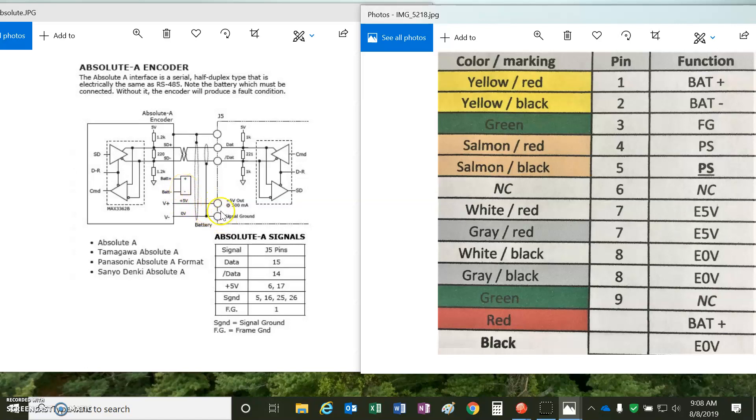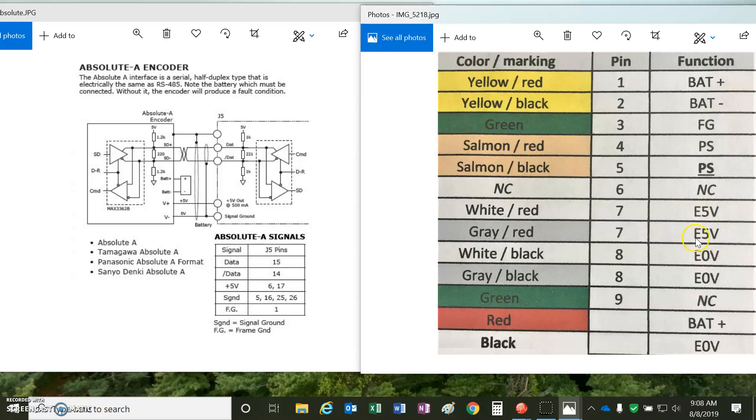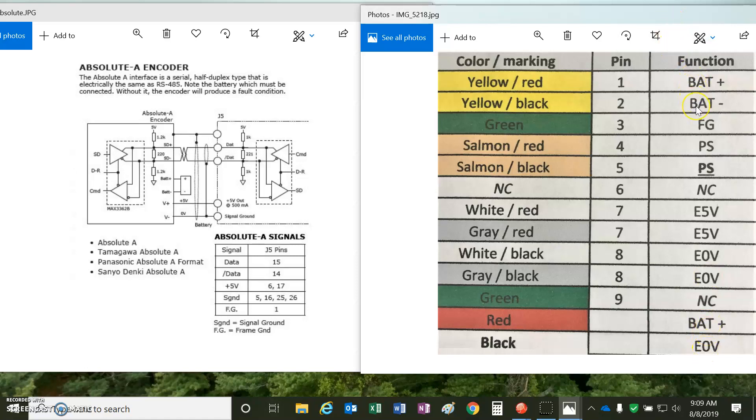And then there's 5 volts to power the encoder. So, this was the wiring information based on the wire colors, and we can see there's two wires for plus 5 volts and two wires for ground. That powers the encoder. There is a battery connection. This may be to charge the battery, and this would be like the battery connection to provide battery power to the feedback device.